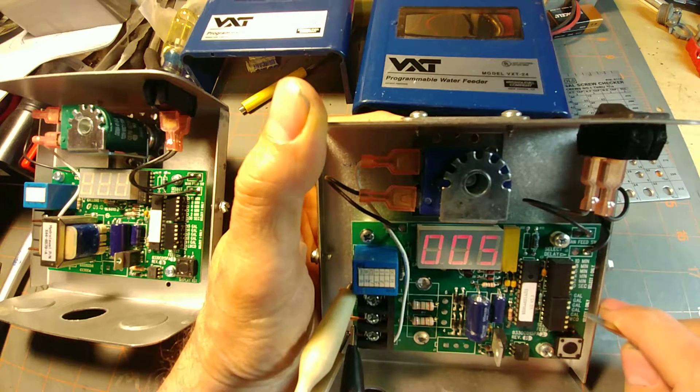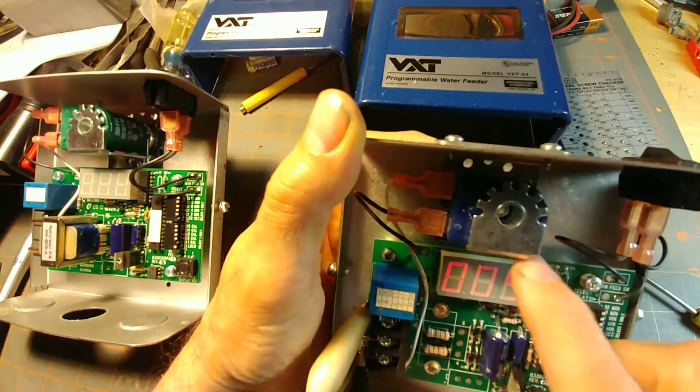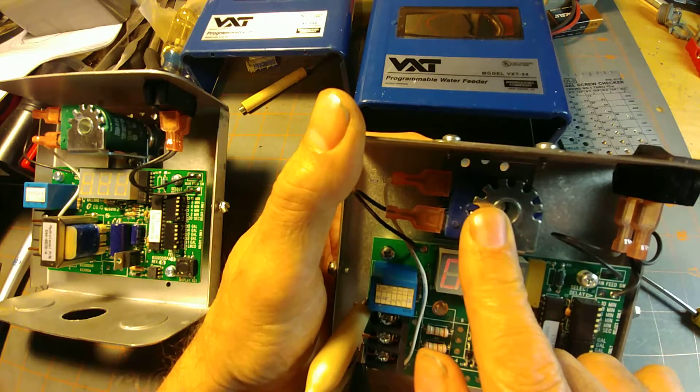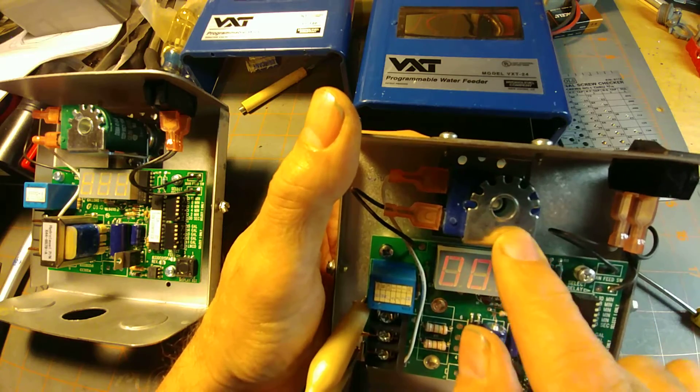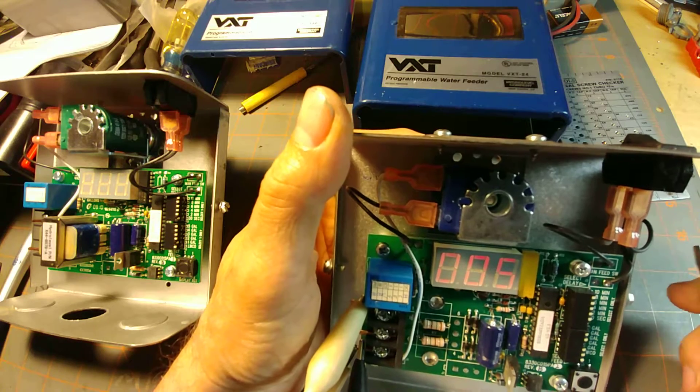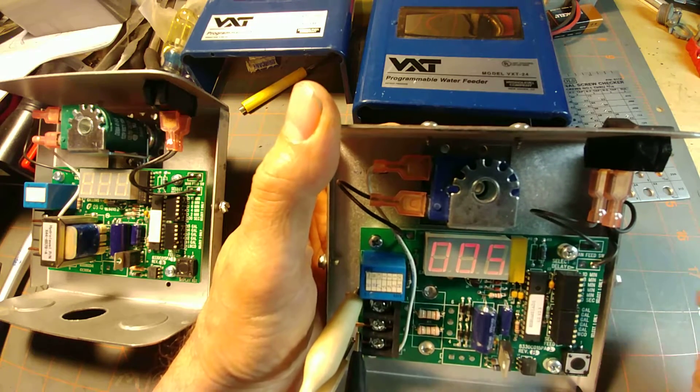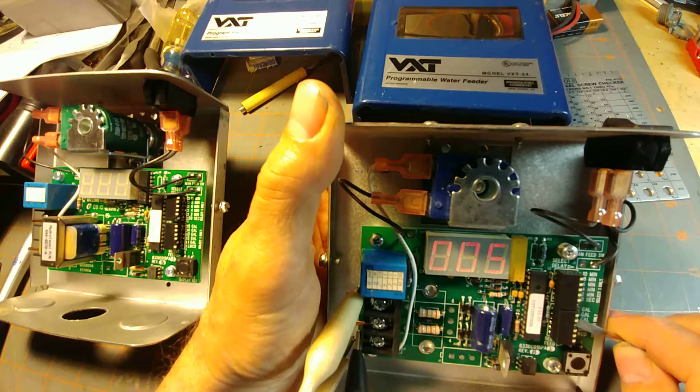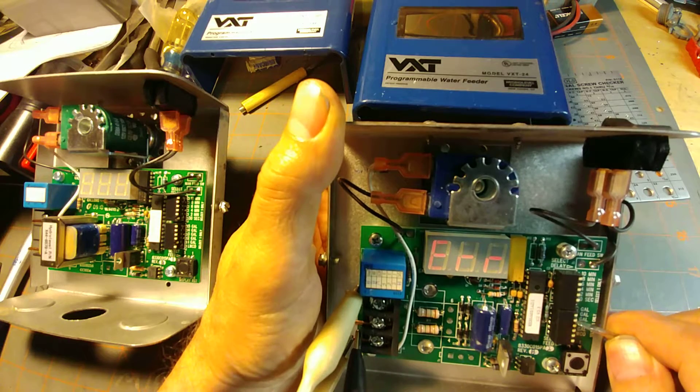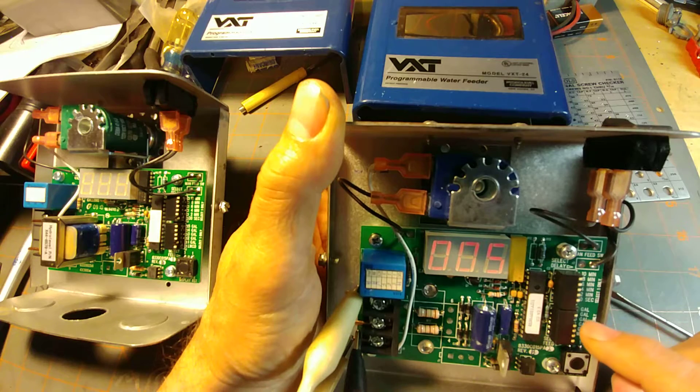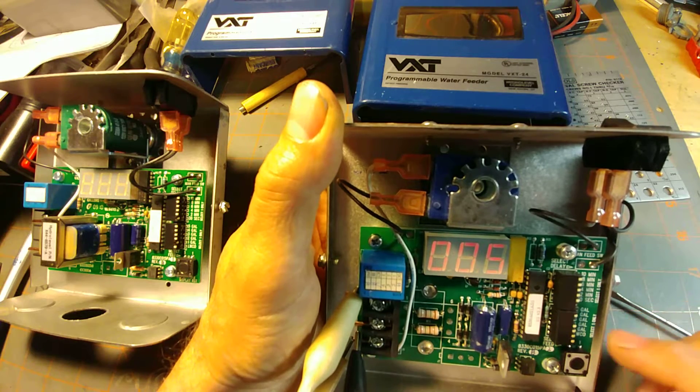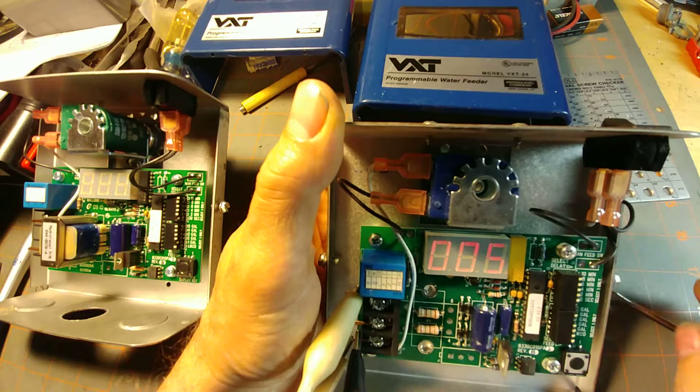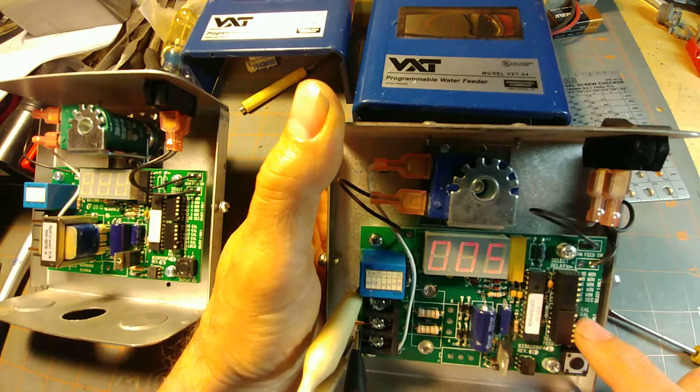Sometimes these things feed very slowly. Remember, it's only giving you a timeout and not actually measuring how much water is really passing through the valve. It's only holding it open for a set period of time. You'll have to experiment as to which one of these settings will fill the boiler about mid-gauge and then shut off per trigger.